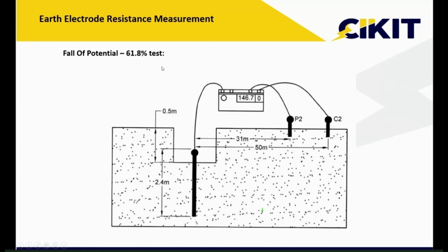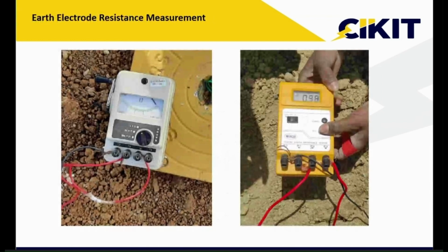The standard has provided different methodologies. Among them, we are using the fall of potential 61.8 method. Here you can observe that the ratio of these two spikes will be maintained at 61 percent. If I'm having the second spike at 100 meter, then the first spike will be at 61 meter. If I'm having the second spike at 10 meter, the first spike will be at 6.2 meter. So we have to maintain the ratio. We can use either analog meters or digital meters for measuring. So this is earth resistance.